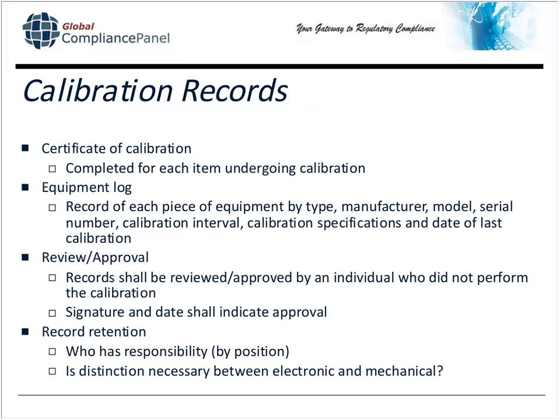We saw an example of one earlier in the presentation. You also want to have an equipment log, because how else does your calibration tech know that a particular piece of equipment is due for calibration at a particular time? So for your calibration log, many people use databases or Excel spreadsheets or commercially available programs. Identify a piece of equipment by type, manufacturer, model, serial number, and date of the last calibration.